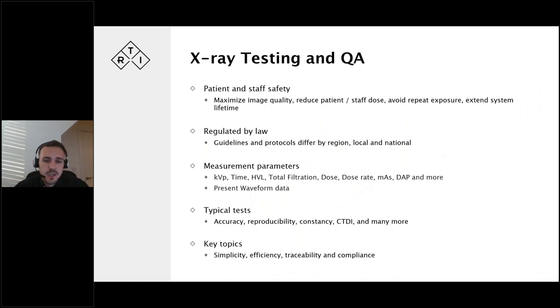So what is x-ray testing and quality assurance? Many engineers will be familiar with the testing process. The main aim of x-ray testing and QA is obviously patient and staff safety - we want to ensure the output of the x-ray tube is as it should be, that we're not giving any more dose, or too little image quality, to the image receptor. So maximizing image quality, reducing patient and staff dose, avoiding repeat exposures, and extending the system lifetime, ensuring the x-ray system is always in peak condition to provide those images.